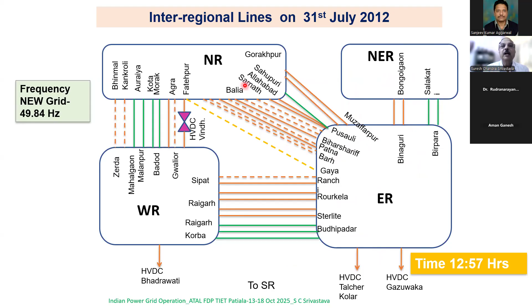So this corridor in the eastern line became very weak. The same thing happened. It again got overloaded, and the reactive power requirement was high. Although 1000 megawatt was flowing, the MVA was high. That line got tripped and this got separated. But the center of oscillation was here because this was the weak transmission network. So Western along with part of Eastern got separated. The rest of the regions were together, but because of a lot of oscillation, first Northern got separated, then a lot of tripping took place in Eastern, and blackout was there in all the 3 regions. Again, this little PMU data actually helped us in correlating the actual event, what had happened.